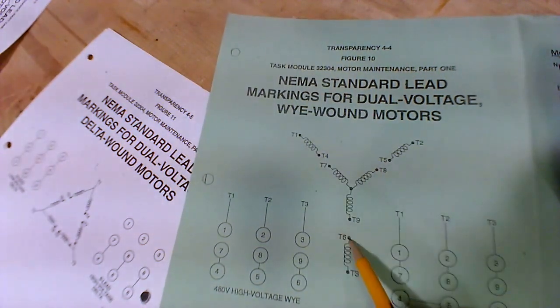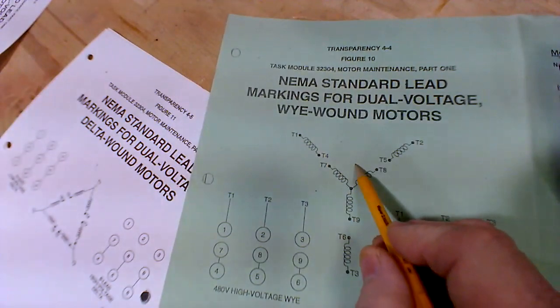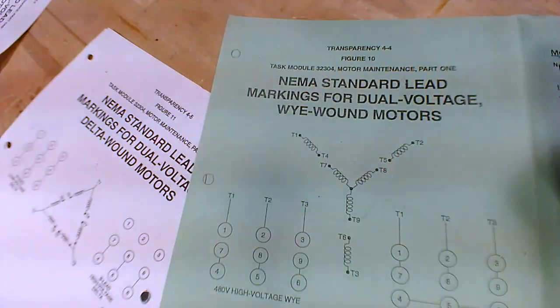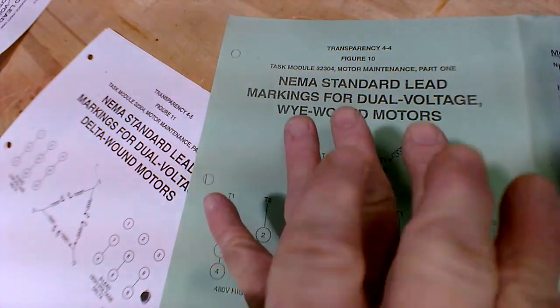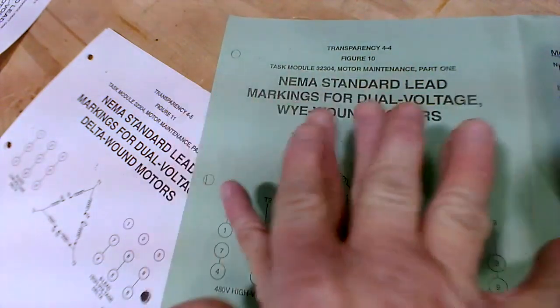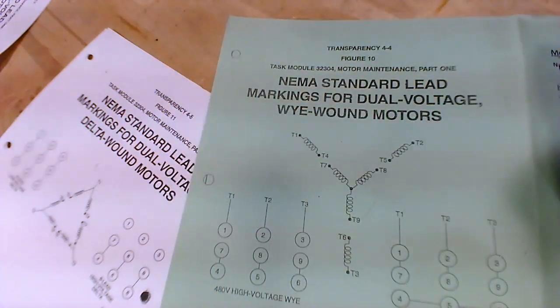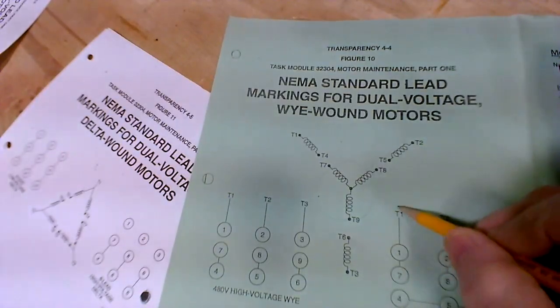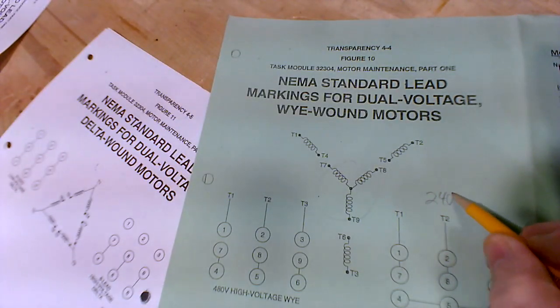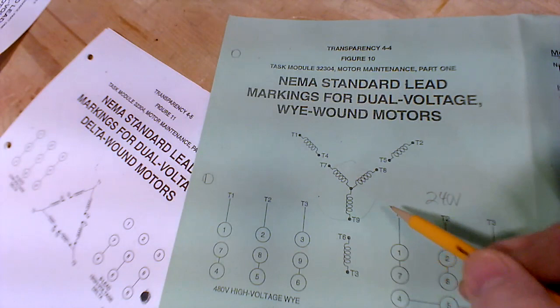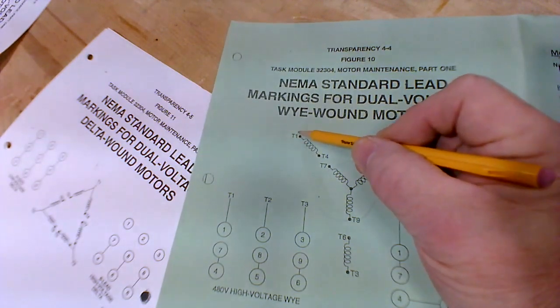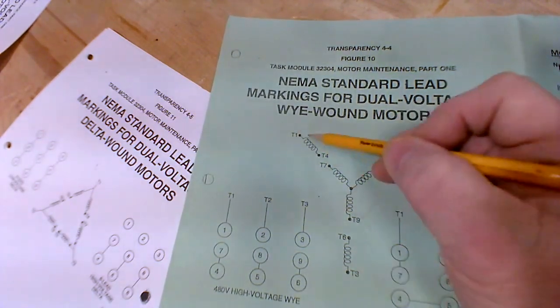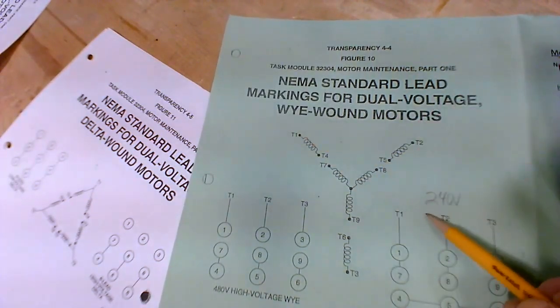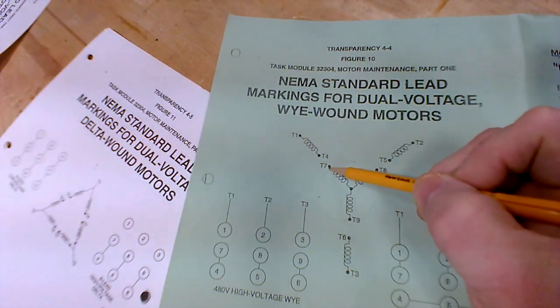4, 5, and 6, whenever you join those together, it forms another Y like this on the outer part. So it's a double Y, and the Y's are in parallel. They're in parallel because of this. Your first leg of the 240, the T1, goes to this outer leg of this one, and it goes to 7 here and here. The same hot leg goes to 1 and to 7.